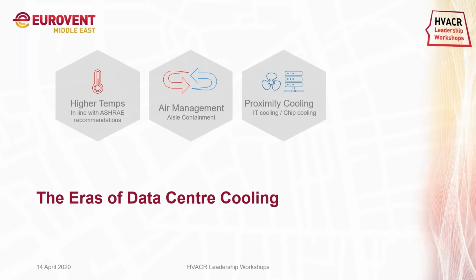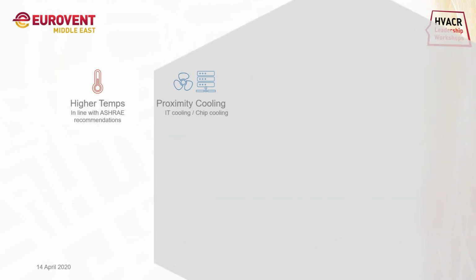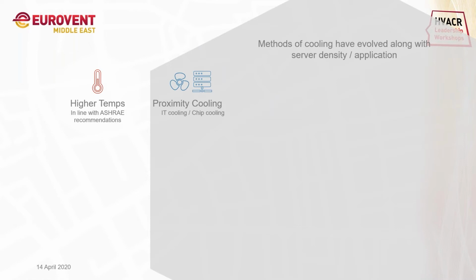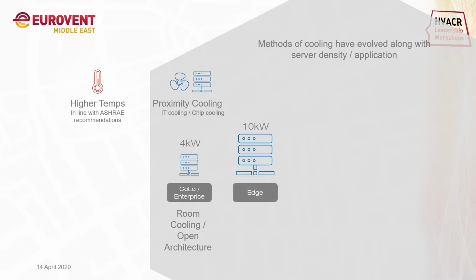Now going to the next area, this is proximity cooling. It is a phrase that we have coined, but it describes the different cooling methods depending on the rack densities. Basically, I will come to that. So methods of cooling have evolved along with server density of applications. For a colocation or enterprise data center where the server density is 4 kilowatt per rack, we are using room cooling or an open architecture or an open aisle.